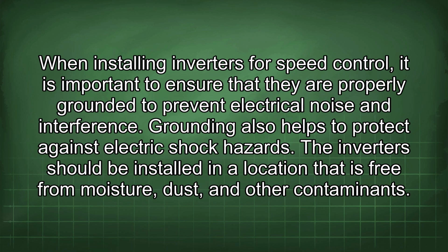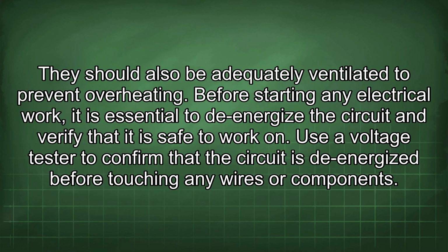When installing inverters for speed control, it is important to ensure that they are properly grounded to prevent electrical noise and interference. Grounding also helps to protect against electric shock hazards. The inverter should be installed in a location that is free from moisture, dust, and other contaminants. They should also be adequately ventilated to prevent overheating. Before starting any electrical work, it is essential to de-energize the circuit and verify that it is safe to work on.